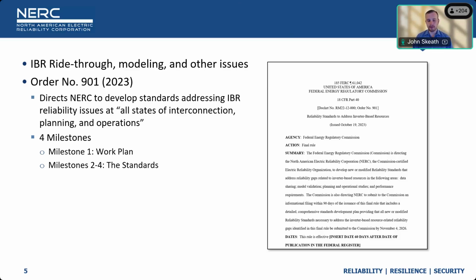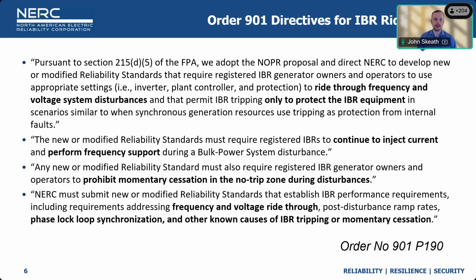This order cites a plethora of disturbance reports from NERC that significantly highlight the state of the land: as system disturbances occur, inverter-based resources trip on various protective mechanisms or settings at the plant, or a variety of different root causes. That led to a significant reduction of exchange of current as seen by the bulk power system. The order highlights in various ways that the ride-through behavior of inverter-based resources needs to become standardized, and PRC-029 does that. Here are some of the highlighted sections of FERC Order 901 that describe the need for standards reform and making sure there is sufficient ride-through performance from inverter-based resources.